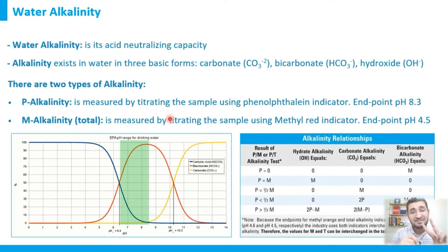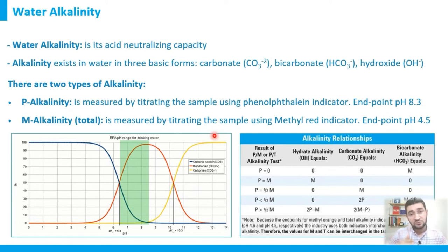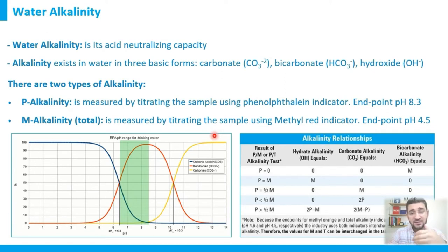The second type is called M-alkalinity, where M stands for methyl red color indicator, used when titrating a water sample with sulfuric acid to neutralize alkaline species. Unlike P-alkalinity, M-alkalinity can be measured for all types of water regardless of pH — whether it is 6, 7, 8, or any other value. M-alkalinity is therefore called the total alkalinity.